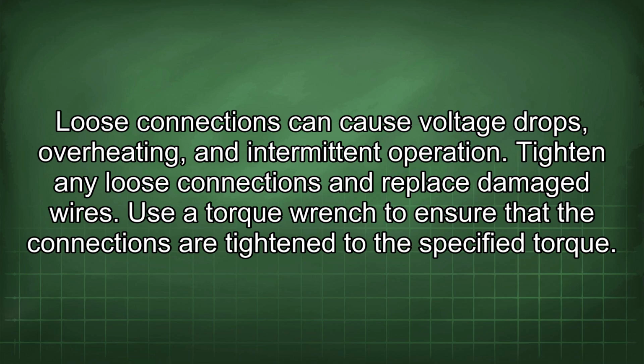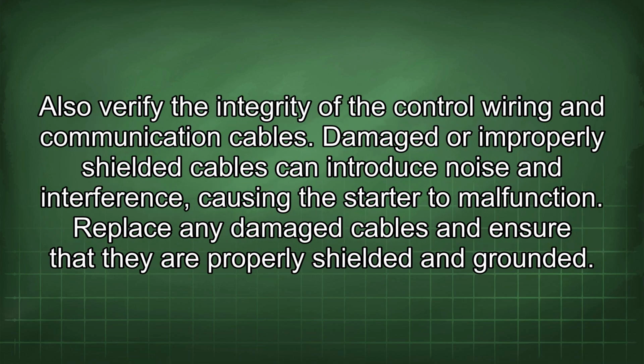Tighten any loose connections and replace damaged wires. Use a torque wrench to ensure that the connections are tightened to the specified torque. Also verify the integrity of the control wiring and communication cables. Damaged or improperly shielded cables can introduce noise and interference, causing the starter to malfunction. Replace any damaged cables and ensure that they are properly shielded and grounded.